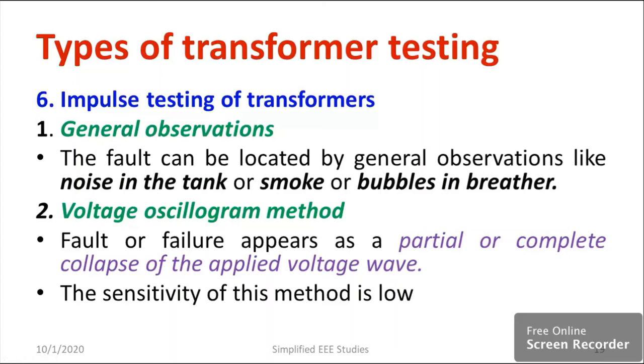Let us understand the peculiarity of general observation. Suppose you are observing the transformer tank where you store transformer oil. If you find any bubble-like structure or any noises in the transformer tank, there is definitely a problem with the transformer insulation. If you found any abnormality — some kind of bubbles, noises, smoke, or other disturbances — we say there is a problem in the transformer oil.